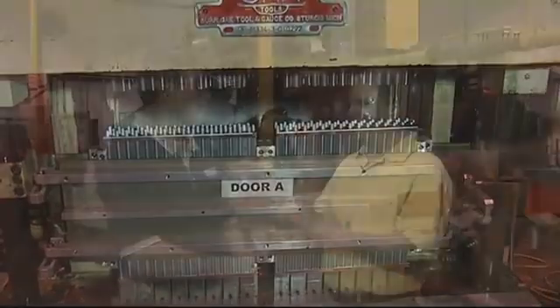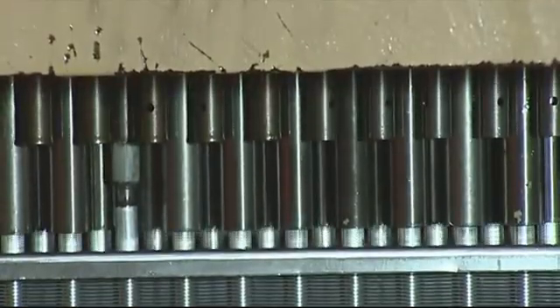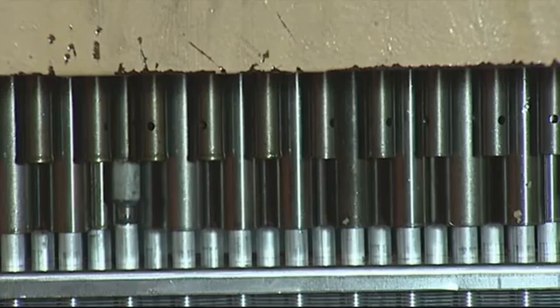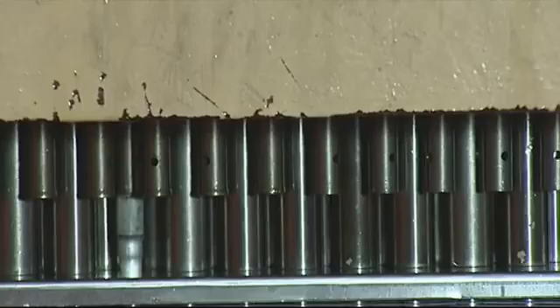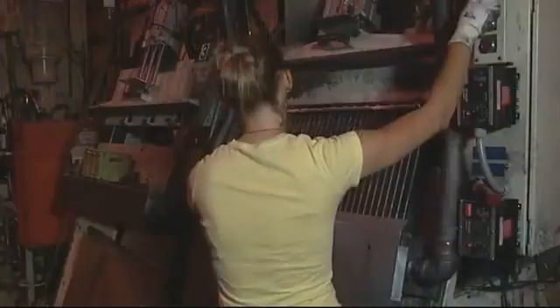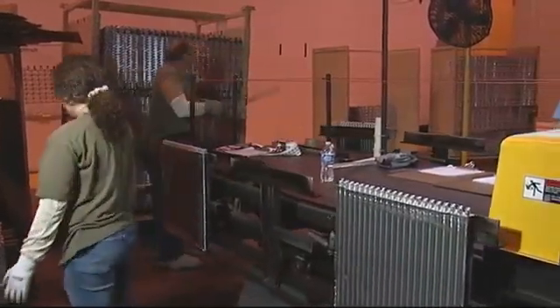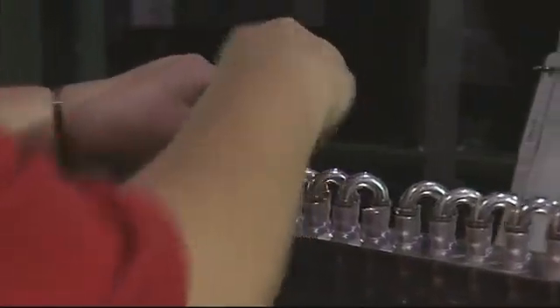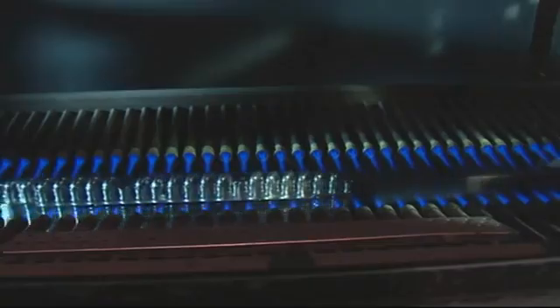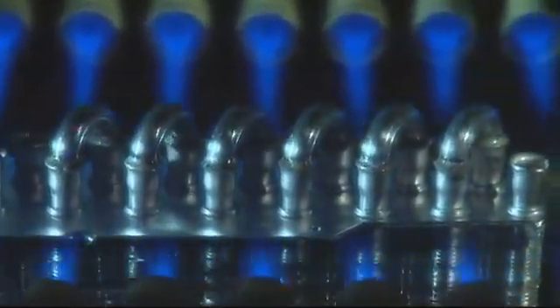What about the expander — what do you do with the fines? We've got special setups on the expander to make sure that the rods and bullets can go down in the tube and expand it out to the fin, but it does create some fines. We've got a proprietary process to remove the fines. And we've got the auto-brazer over here as well. Part of that process is proprietary too — we've got special braze rings, special return bends, and we run it through. We've got various setups for raising the return bends and crossovers into the coil.